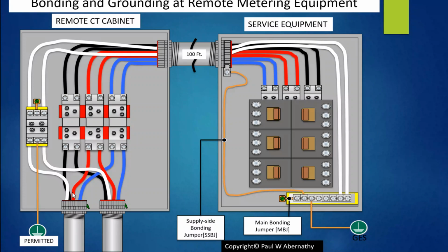Now I don't have to have any jumper over here because these bonding lock nuts meet that requirement and it's all good to go. This raceway in the middle here that's connecting the two, again, that is already bonded on the side where the service equipment is, and we just sized that a second ago. I don't have to do both sides. I only have to do one.